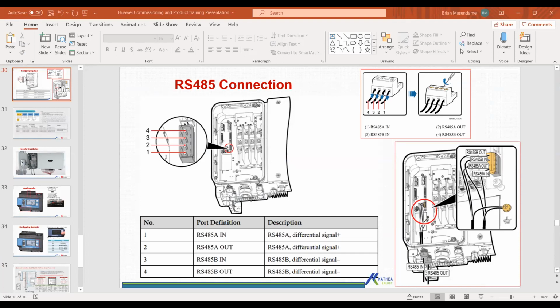What if I have two inverters that are 200 meters apart? How do I get them to communicate? The RS-485 line can go up to 900 meters preferably, but the RS-485 daisy chain can go up to 1,200 meters. So you can hook up your inverters through an RS-485 line. Unfortunately, Huawei does not support remote devices, because they will disconnect over time and affect control. So they prefer hard wiring. So you can wire your inverters through an RS-485, and the daisy chain can go up to 1,200 meters without a problem.